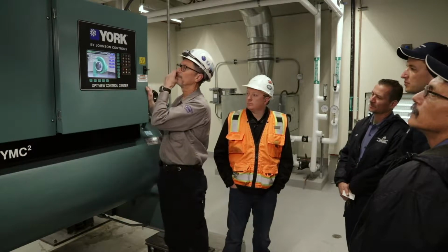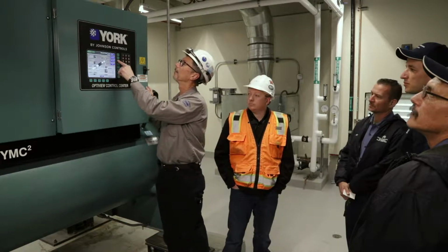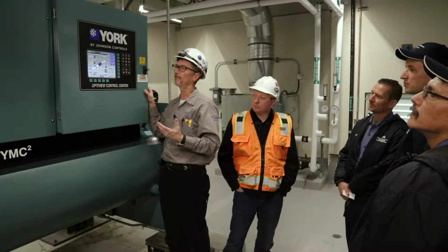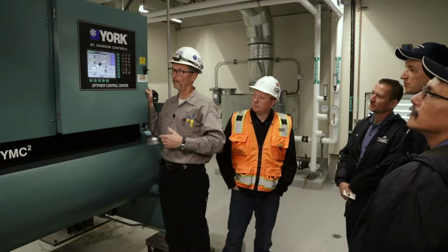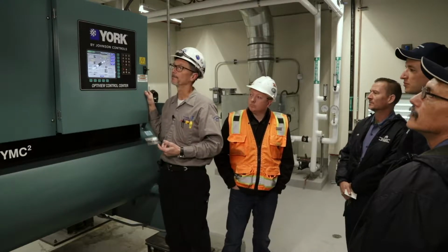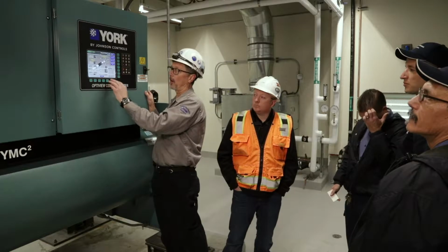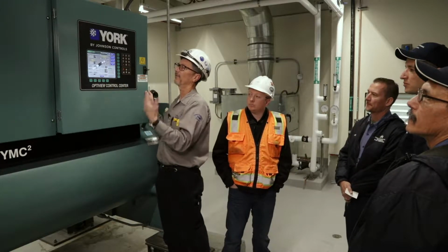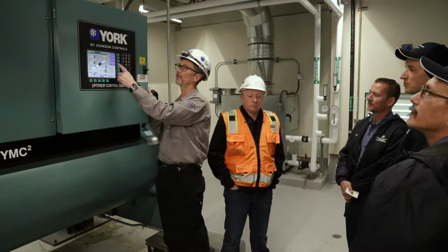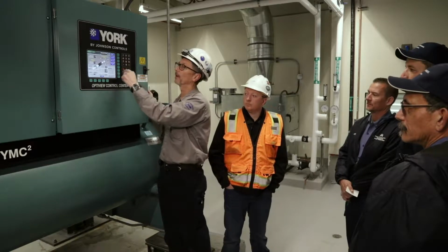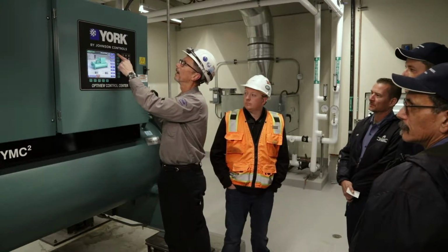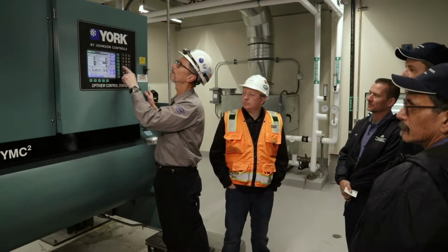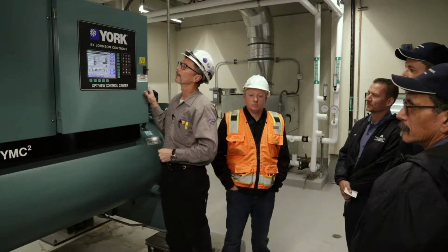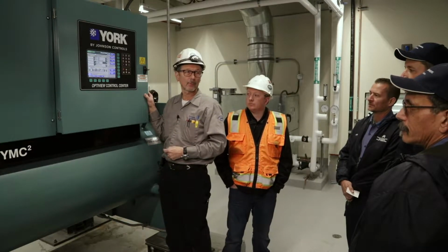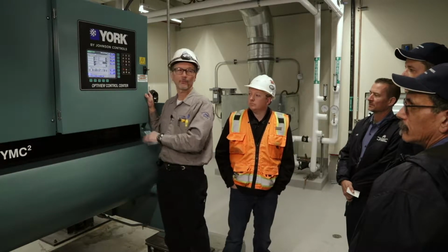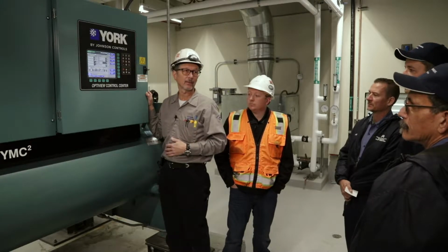Let's go down to the compressor screen. The magnetic bearing screen shows what's happening with the magnetic bearing during the run cycle. What position the bearing is in, or the shaft is in. And you can see alarms that are happening in this screen as well. If an alarm was happening, it would alert you, and a soft key would show up and you would go to that alarm. Capacity control basically is all the different levels of limits that you want to place on the machine, and we'll have to go through that more in depth at some other date. There's a lot more to that.